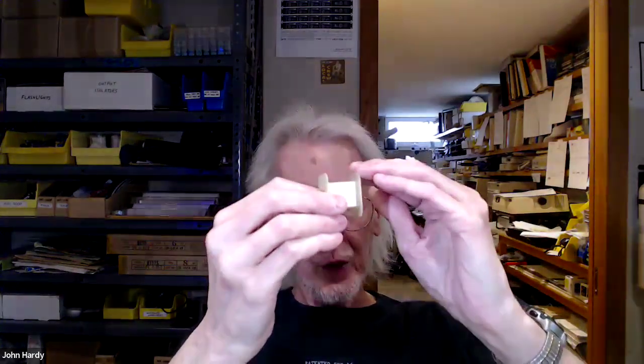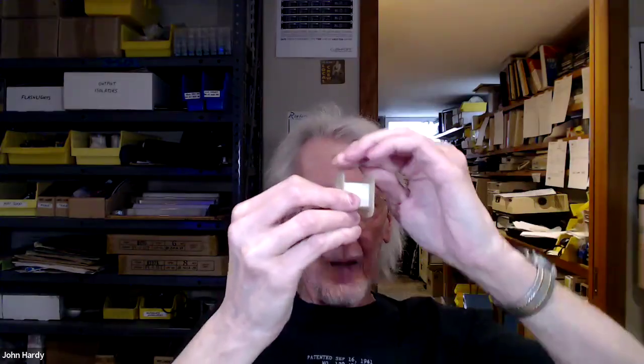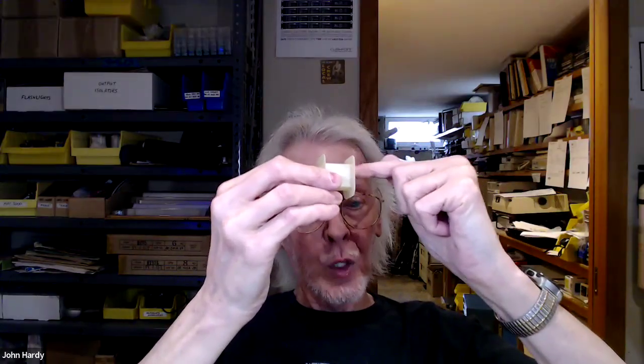So I decided, rather than route the wires down or up the walls, to have them come straight through the side wall of the bobbin where they need to be, to either start a winding, end a winding, or terminate a shield. That should make more uniform windings, because otherwise the winding has to detour around those wires and the tape holding them in place. It just seems like common sense to me.